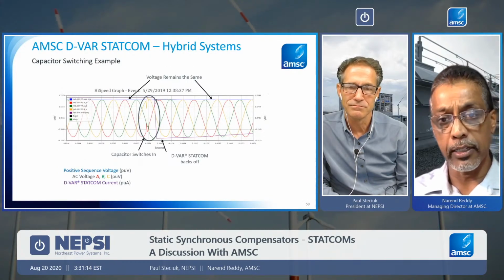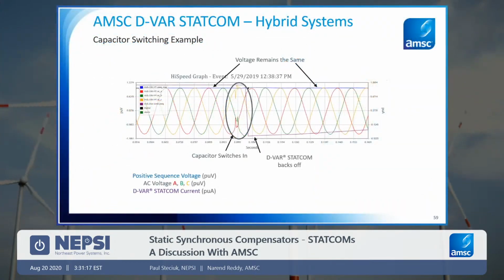Now, I just wanted to show you in an example, what does this soft switching capability really mean? You know that when you switch in a single step cap bank, you'll get a step change in voltage. Let's say you switch it in, you'll get a certain rise in the voltage. But when we do soft switching of these capacitor banks, you will note this is an actual capture of the voltages during a switching in of a capacitor bank, sorry. You will see that when the cap bank is switched in, there are some momentary transients. Now, these are transients based on the inrush current and the system impedances at a high frequency, and the DVAR does not address that.